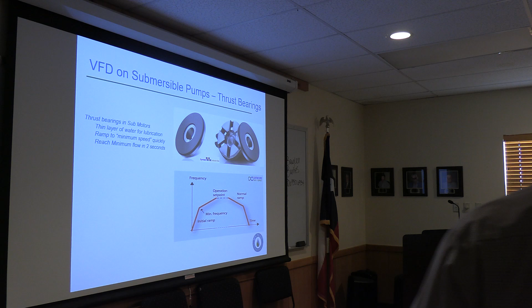If you've got a variable frequency drive on a vertical hollow shaft or a motor that's isolated from the pump, you can spool that up for a week if you wanted to, and it won't really make a difference. But with the submersible, you have to be cautious of the thrust bearing in it, so your ramp needs to be pretty quick. Essentially, the recommendation from Franklin that was on the other page is you need to reach minimum flow in 2 seconds.